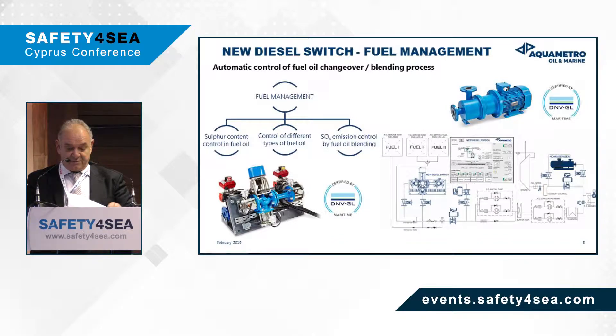When it comes to fuel management tools, we are proposing the use of our new diesel switch, whereby one can control the sulfur content in the fuels. Our system can control different types of fuels, and also control SO2 emissions by fuel blending. It's a fully automated process done in a controlled manner, and our diesel switch can blend from various tanks and, by the use of a homogenizer — which helps against incompatibilities and instabilities — deliver a smooth, fine fuel to be burned in the combustion chamber.